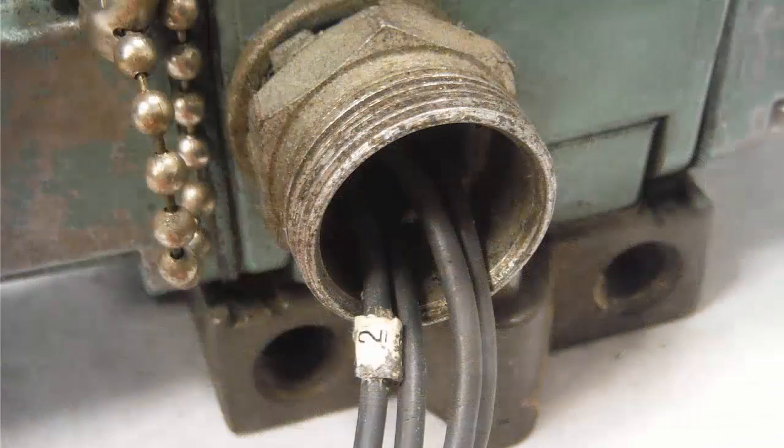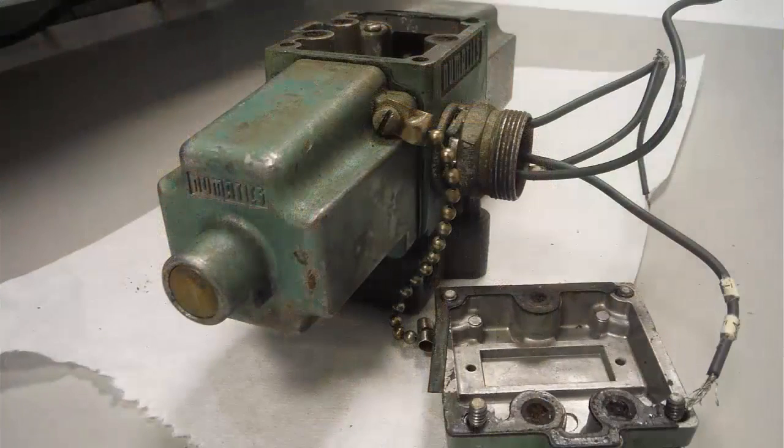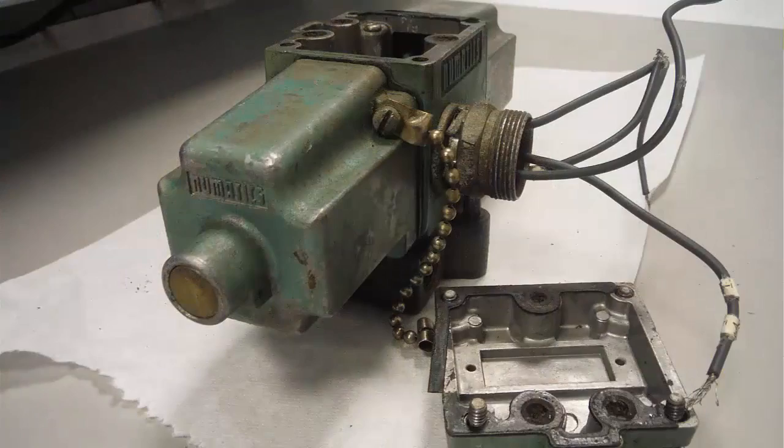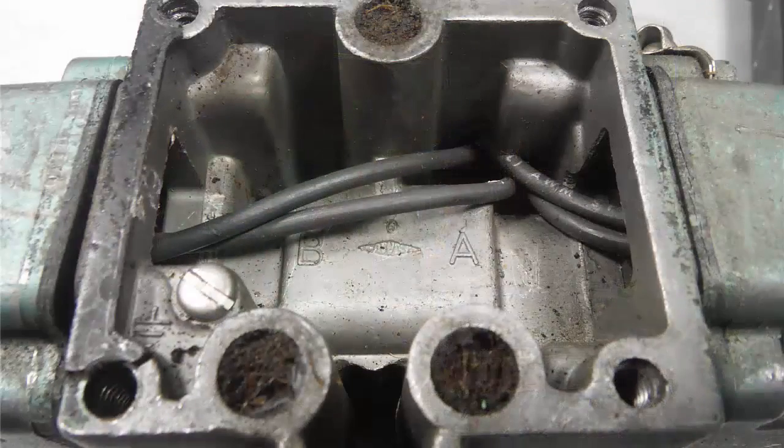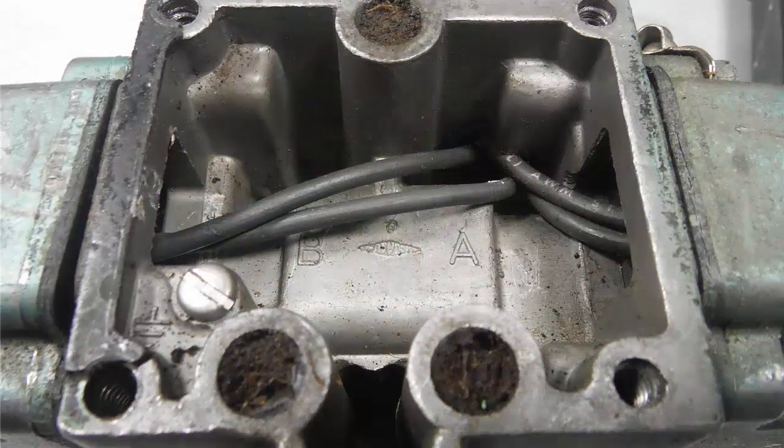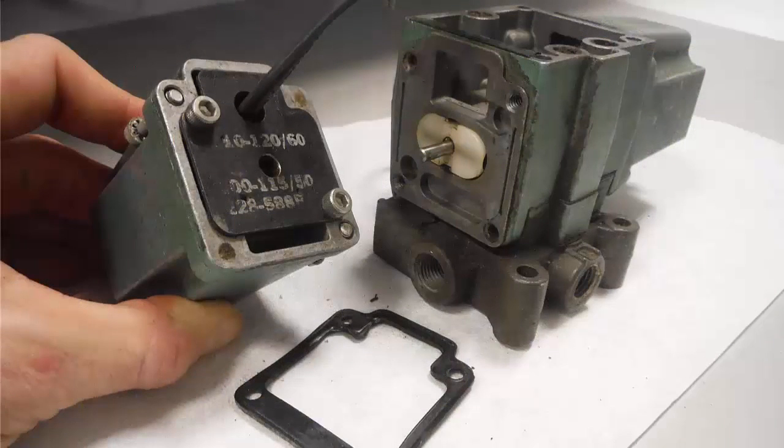The base plate features stamped port markings obscured by generations of accumulated sawdust. The electrical connections to the two coils poke out the back. If these wires weren't labeled, you can pop the top off the valve to see which connection goes to which coil. Notice A is stamped on the right and B is stamped on the left.